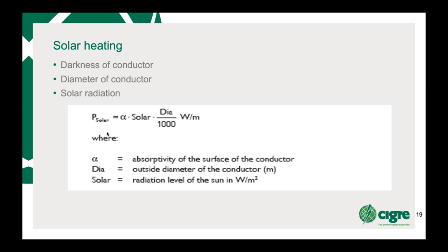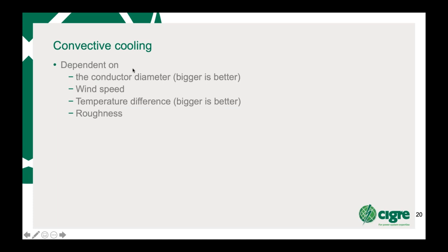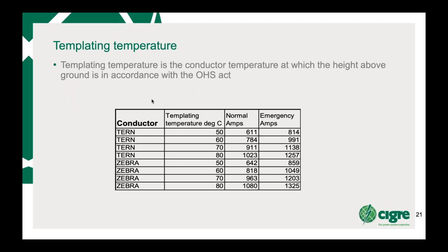Looking at convective cooling, this is cooling due to the wind. It's dependent on the conductor diameter. Bigger is better. On the wind speed, and the temperature difference between the conductor and the ambient temperature, the bigger is better. And then the roughness factor. If you've got a smooth conductor, it doesn't cool as well as a conductor with very large strands. The other thing, of course, that affects the thermal rating is the operating temperature. And here we can see the variation on Tern and Zebra, where if you go from 50 degrees to 80 degrees, you can almost double your thermal rating.